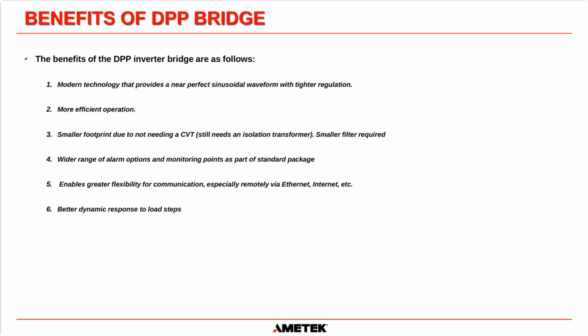DPP is more efficient. One of the downfalls of the ferroresonant design is that we have to saturate that transformer, and that takes energy. That transformer is saturated all the time, so that's kind of wasted energy and heat. But with the DPP, it's more efficient. We are energizing the output transformer, but we're not saturating the transformer. We're not wasting as much energy in heat in the inverter bridge design.